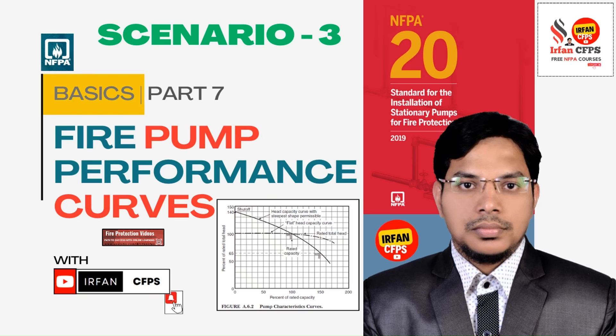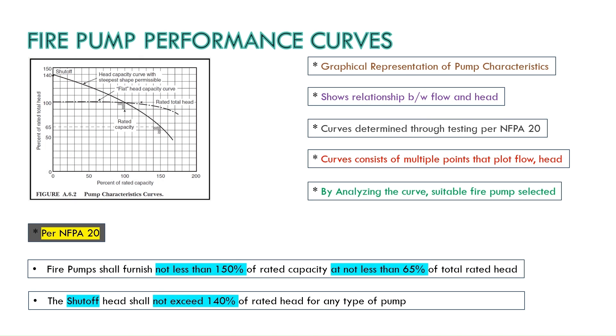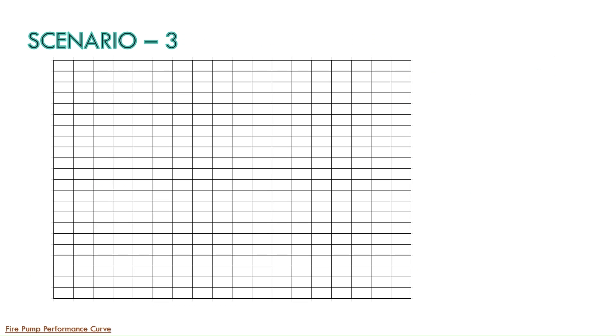Hello everyone, today will be an interesting session since we are going to consider Scenario 3 in order to draw the fire pump performance curves. We are going to skip this particular portion since it was already discussed in our earlier video. So we are going to look at Scenario 3 and consider one example. As you can see on your screen, the water supply is from an above ground water tank and the static pressure available is 33 psi, and the building is protected with a wet pipe sprinkler system.